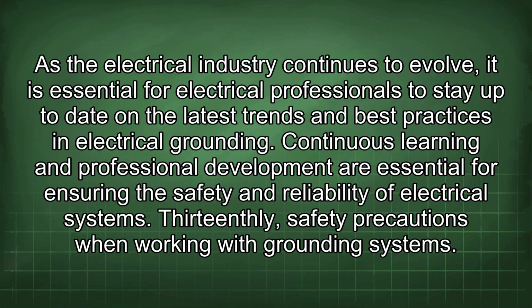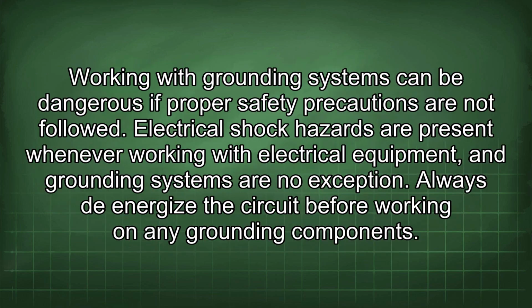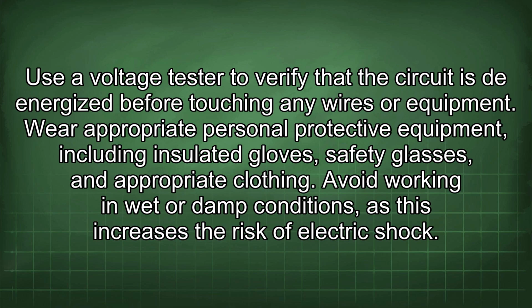13th, safety precautions when working with grounding systems. Working with grounding systems can be dangerous if proper safety precautions are not followed. Electrical shock hazards are present whenever working with electrical equipment, and grounding systems are no exception. Always de-energize the circuit before working on any grounding components. Use a voltage tester to verify that the circuit is de-energized before touching any wires or equipment. Wear appropriate personal protective equipment, including insulated gloves, safety glasses, and appropriate clothing. Avoid working in wet or damp conditions, as this increases the risk of electric shock.